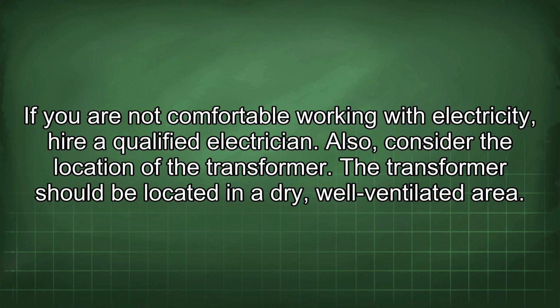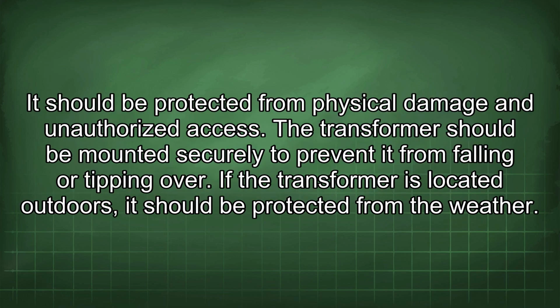Also, consider the location of the transformer. The transformer should be located in a dry, well-ventilated area. It should be protected from physical damage and unauthorized access. The transformer should be mounted securely to prevent it from falling or tipping over. If the transformer is located outdoors, it should be protected from the weather.